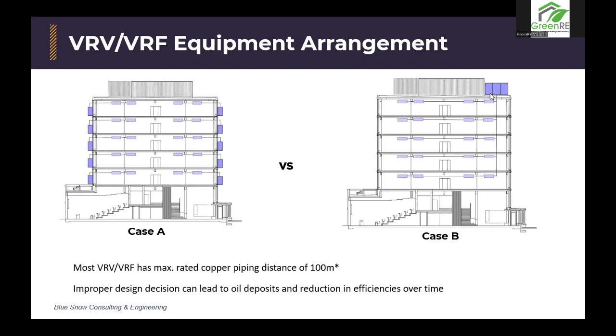Then you may need to change the VRV's outdoor unit every 7 or 8 years. It's not that this config is bad. It's just that you need to be a bit more careful and a bit more diligent in making sure that your contractors and your designers have actually sized the copper pipe. It will be as detailed a calculation as we would normally do for chilled water piping. But again, based on our experience, those that do case B don't really do that calculation.